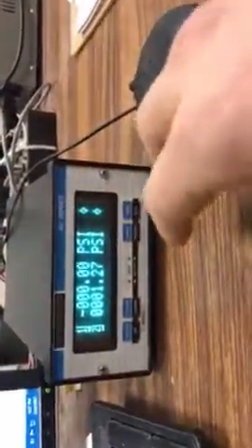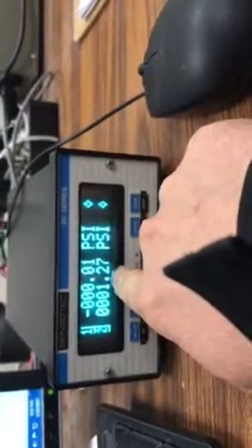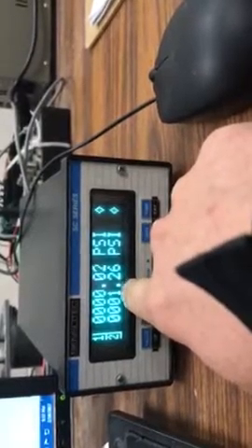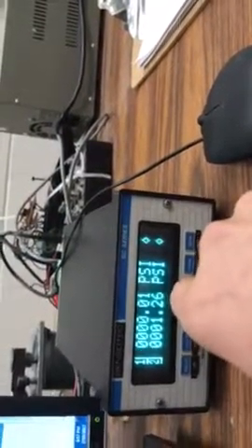And then I hit run here. The signal is starting now, but the system is not stable yet, and I'm waiting a little bit until it becomes stable. As you can see here, the upstream transducer is reading some static pressure in PSI. This has been set up based on the calibration in PSI units. And here the water is coming, and these are my signals, the pressure in my system basically. It will not take long until the pipe is fully filled with water. Just waiting a little bit. I think now it's full.